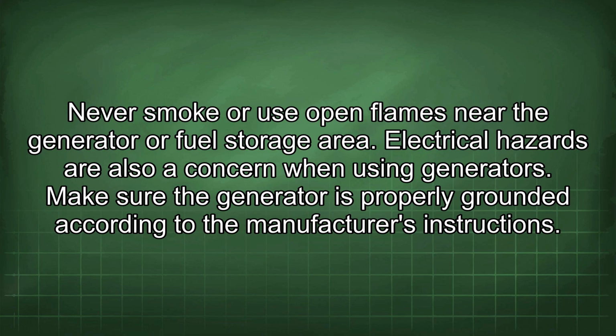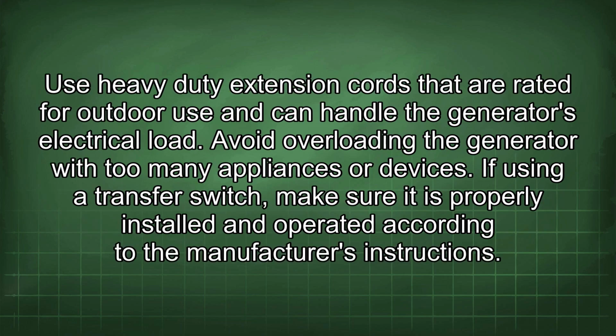Electrical hazards are also a concern when using generators. Make sure the generator is properly grounded according to the manufacturer's instructions. Use heavy-duty extension cords that are rated for outdoor use and can handle the generator's electrical load. Avoid overloading the generator with too many appliances or devices.